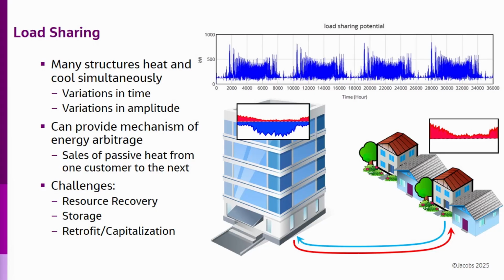With geothermal energy networks, if we get into a lower temperature regime like Connor mentioned, somewhere between 40 and 90 degrees operating across a season between highs and lows, you can also introduce load sharing. As one heat pump rejects heat to a hydronic network, another building along the route may be extracting heat from that network, which reduces primary energy consumption across our cities. That's a resource you can tap into to decrease capital costs and mitigate emissions from the system, even in Scope 2.